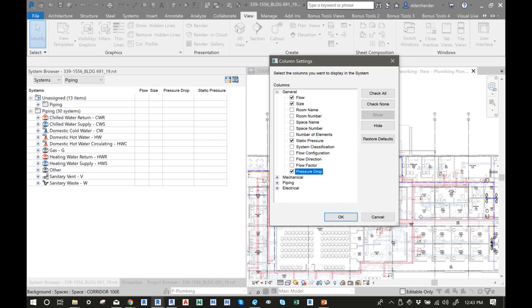I set up a view with a duct system, tagged the size of the duct, tagged the flow, and did an ISO, and gave that to her. Instead of having to take a scale and measure the plans over the length of the ducts to put into her spreadsheet, she could just look at this and say, okay, this duct is 6 inches with 100 CFM, it goes to the next fitting here, and then another one adds on for another 200 CFM, and that 200 CFM has got 5 feet 9 inches or whatever. Instead of having to measure that, she could just plug the numbers into her spreadsheet, so it was a big help just being able to do that.